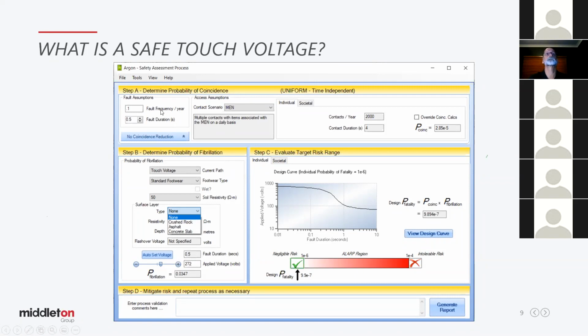In this case, we'll look at the probability of coincidence, as we spoke about earlier. So what's the fault frequency? Obviously, the more faults per year, the more likely someone's going to be in a hazardous situation. The longer the fault is there, obviously, the more likely the person is going to experience fibrillation due to the coincidence.